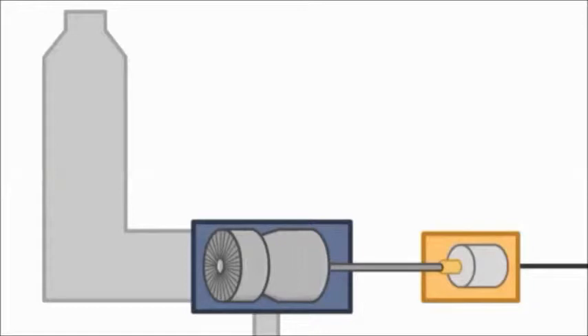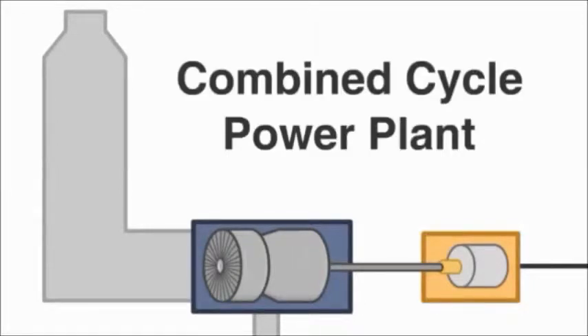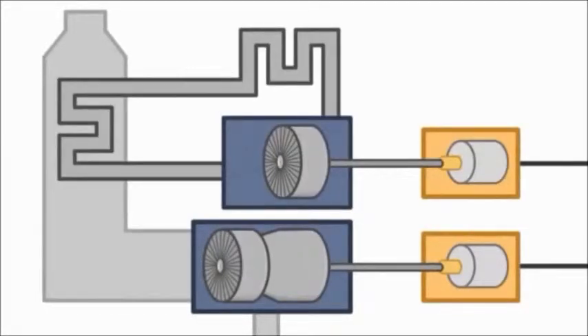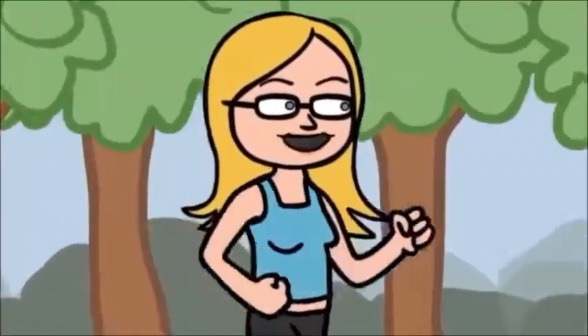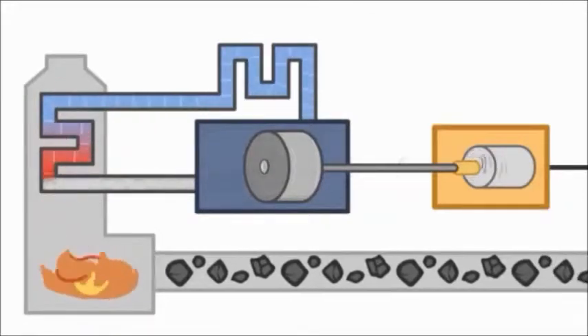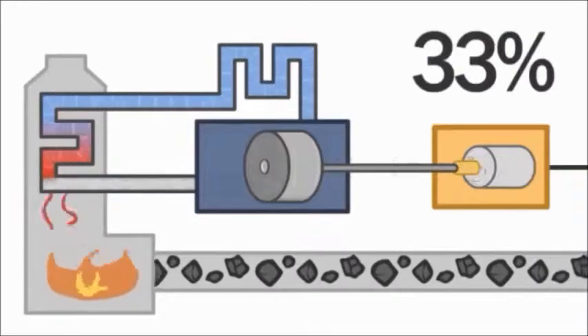There's also a second type of natural gas plant called a combined cycle power plant. It combines a gas turbine and a steam turbine used in a coal power plant. But instead of using coal, or even more gas to create steam, a combined cycle plant uses the exhaust heat from the gas turbine to boil water into steam. The steam then drives a second turbine, which spins a second generator, producing even more electricity. This two-step combined cycle process is highly efficient, converting as much as 50% of the energy contained in natural gas into electricity. In comparison, coal-fired steam turbines are only about 33% efficient.